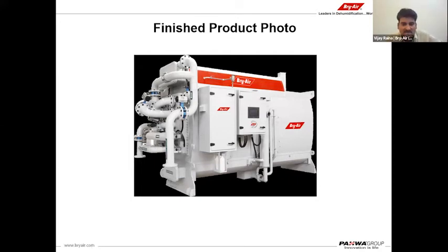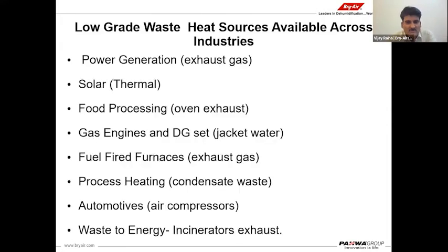And this is the finished product, a factory tested product for chilled water generation based on low temperature hot water, which ranges from 60 degrees to 90 degrees. So low grade heat source is available across the industries. Every power generation plant has exhaust available. Solar thermal is for commercial application, and if it is a small CHP application for commercial buildings, we can also use that heat in our adsorption chiller.